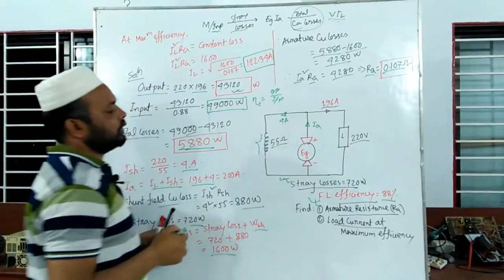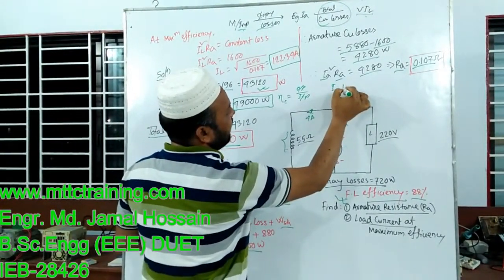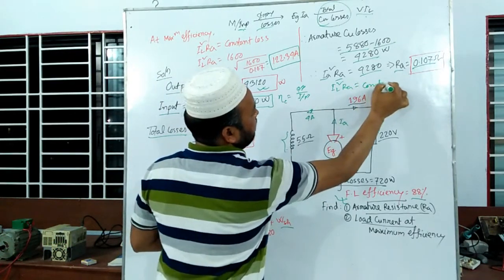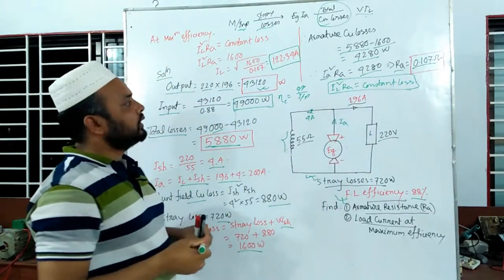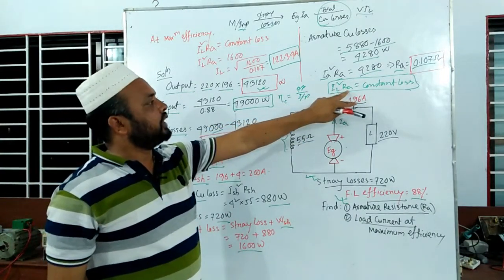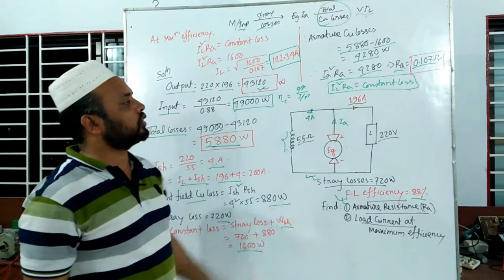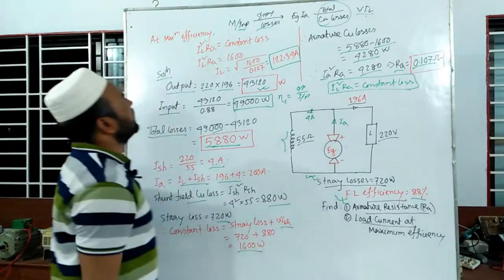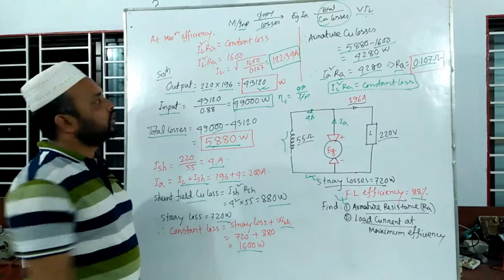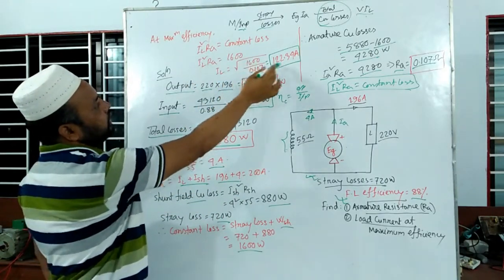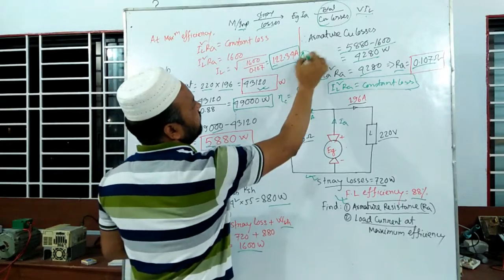The load current is at maximum efficiency. When the load current is at maximum efficiency, it is shown to be lower than the overall full load current. The load current at maximum efficiency is where the constant loss equals the variable copper loss — the amount reduces to near zero. So at maximum efficiency, the constant loss equals the variable loss.